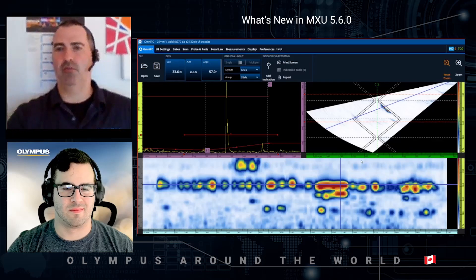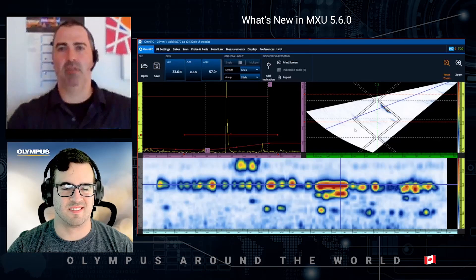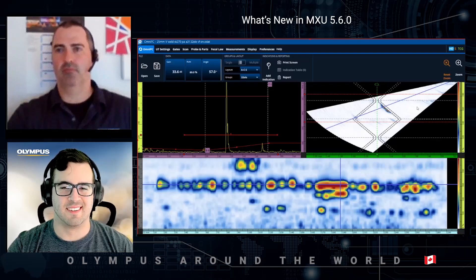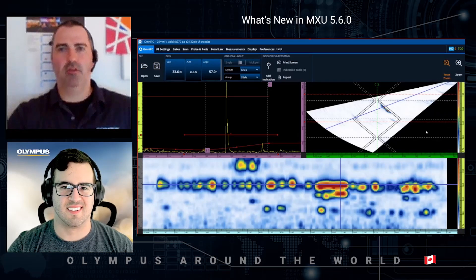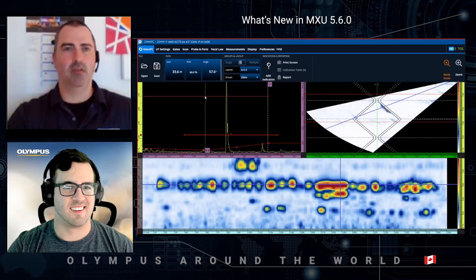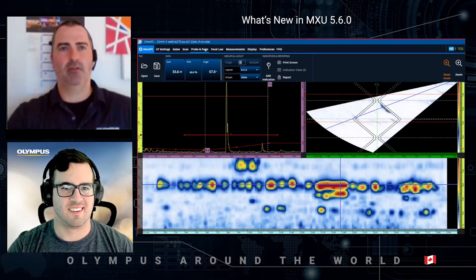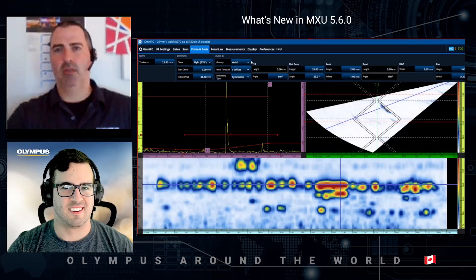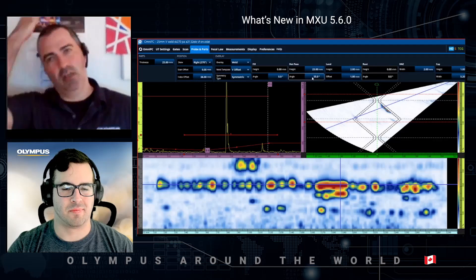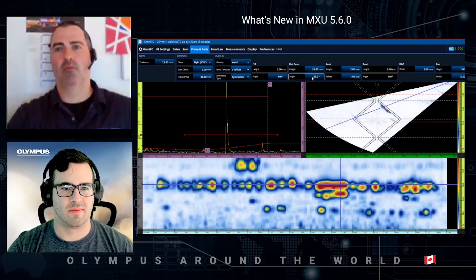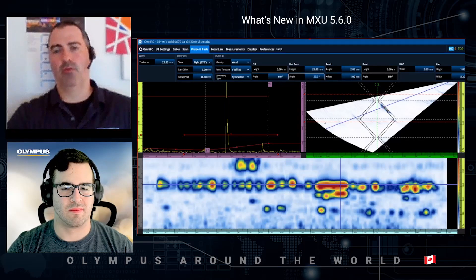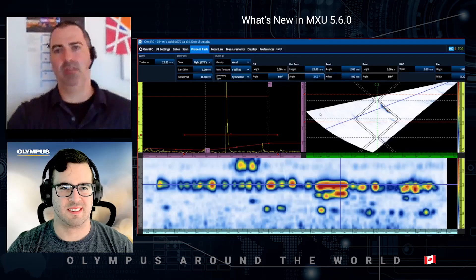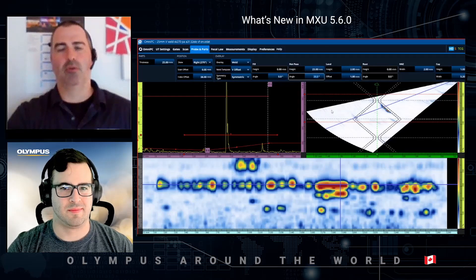It's a simple download and you don't need any security dongle — you just need a PC that meets the requirements. Under Probe and Part you have all of the available weld parameters. In case the weld changes throughout the scan length, or one or more parameters were not correctly set, you can adjust them in analysis, whether you're using OmniPC or the onboard MXU software.